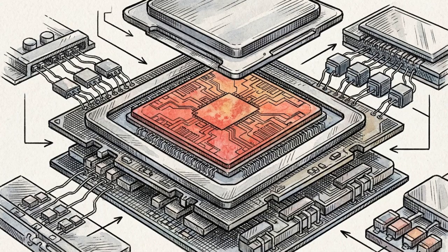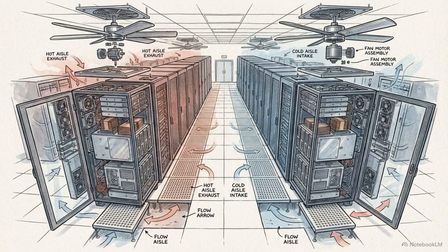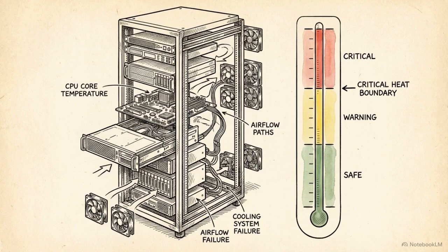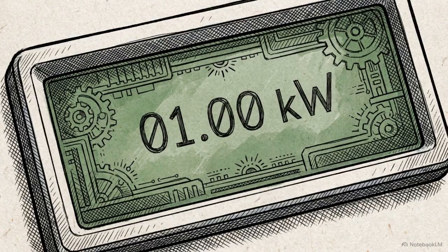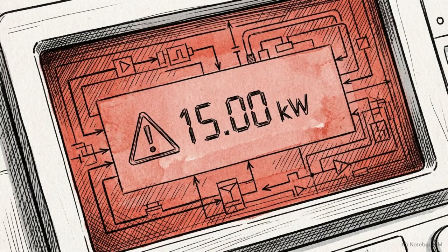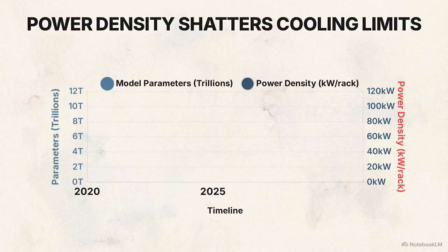All that concentrated computation generates an enormous amount of heat. We are colliding with a strict physical constraint known as the thermal wall. For decades, data centers have relied on moving air to keep servers cold. But traditional air cooling designs max out at supporting roughly 10 to 15 kilowatts of power per rack. A kilowatt is simply a standard measure of electrical power consumption, and 15 is the upper limit of what airflow can realistically handle. This chart illustrates the severity of the gap.